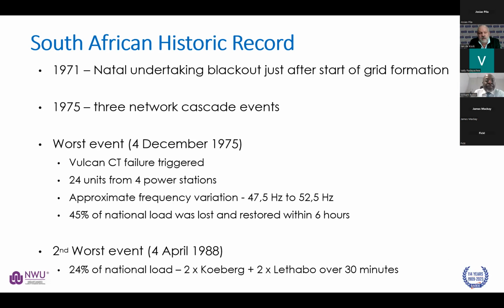It was a result of a CT failure at Balkan substation near Witbank. 24 units at 4 power stations tripped, and the frequency varied from somewhere around 47.5 hertz up to 52.5 hertz. And 45% of the national load was lost in this period, and it was restored 6 hours later. The second worst event was on the 4th of April, 1988, where 24% of the national load was lost. This was a result of 2 units at Koeberg tripping and 2 at Lethabo, and that happened over a period of 30 minutes.